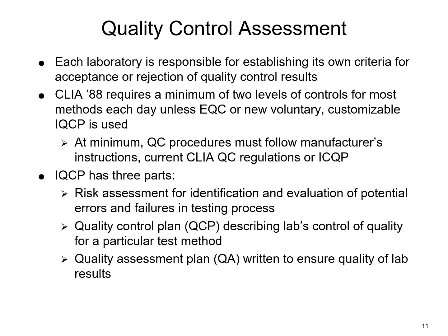Now, if you developed an IQCP plan for a particular analyte, does it take away from you still having to do quality control? No, it does not. It's just for certain procedures where the manufacturer has determined that this particular analyzer, for example, iStats. iStats are a point of care test that can be done bedside, but a lot of places will use them as their chemistry test panel or troponin test panel in the ER, different things like that.